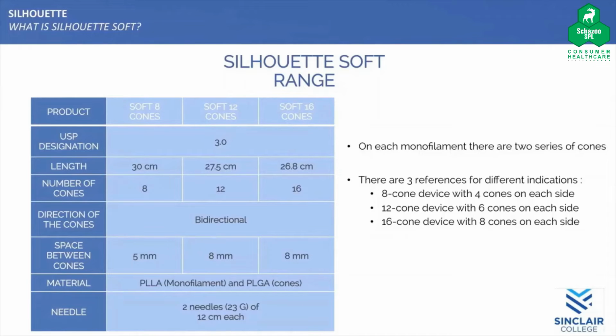The monofilament measures 30 cm, with cones separated by tied knots placed at 5 mm of each other. The 12-cone device is presented with 6 cones on each side. The monofilament measures 27.5 cm, with cones separated by tied knots placed at 8 mm of each other. The 16-cone device is presented with 8 cones on each side. The monofilament measures 26.8 cm, with cones separated by tied knots placed at 8 mm of each other. In order to facilitate its insertion in the tissue, the Silhouette Soft device has two 12 cm 23G straight needles attached to each end.